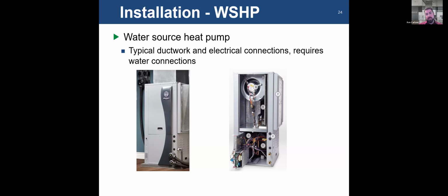Your water connection from your geothermal system will get connected to here. There's the heat exchanger in this bottom cabinet, and that's going to be your transfer medium in cooling and heating, right? So again, this would be self-contained for the most part. When installing, you would be in charge of connecting your ductwork, your electrical, and your water lines. They come pre-charged. It's all ready to go. It just needs to be started up once everything's connected.